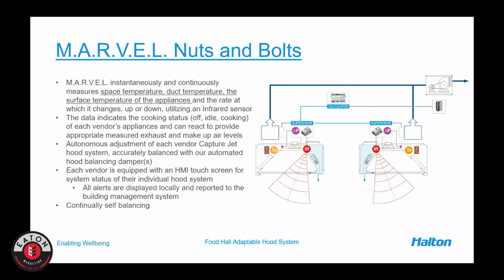This slide talks briefly about the components involved in the M.A.R.V.E.L system. It's a very smart hood system in that it uses controllers on board at each hood, as well as a master PLC. We have pressure transducers on board at each hood also. That's a very key component because that is what allows us to measure the airflow at each hood. We calibrate these hoods through laminar flow elements, so we know at a very specific static pressure how much air is being exhausted through that hood.